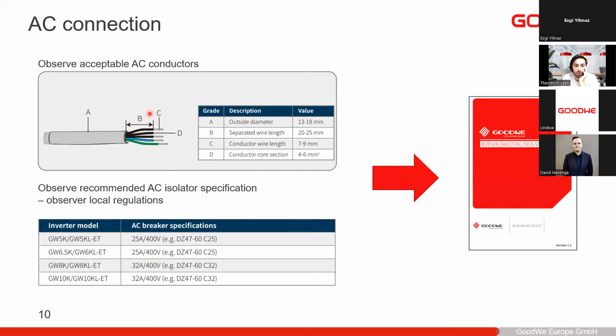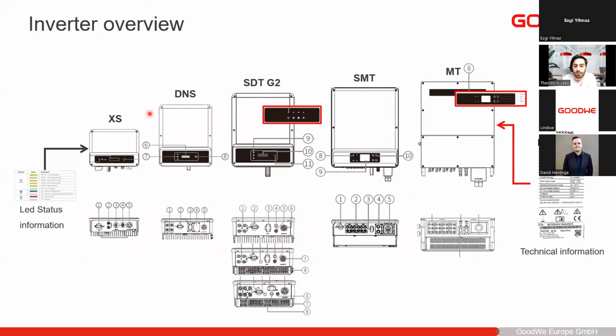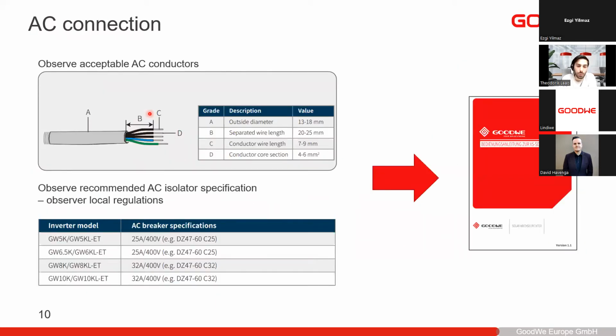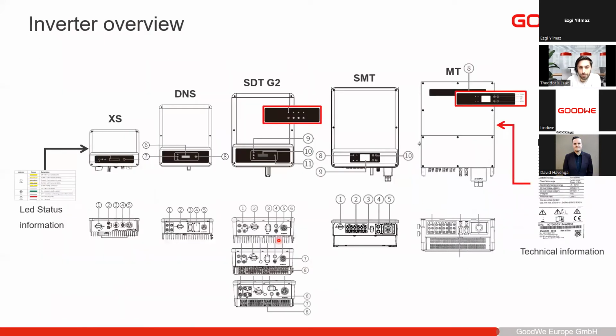It's also recommended to use AC breakers between the inverter and the grid connection. Here you need to size them properly, and we do recommend that you have 1.25 times the rated output current of the inverter. You also see the specifications in the user manual, so make sure that you check this as well.